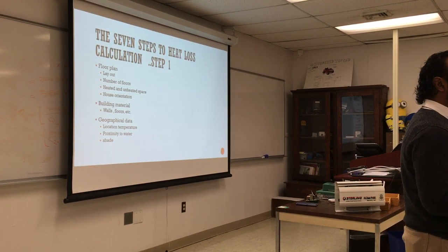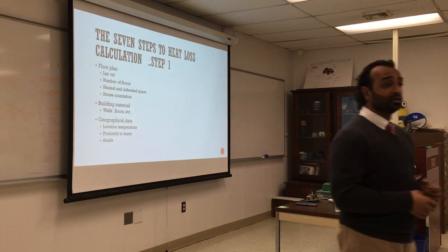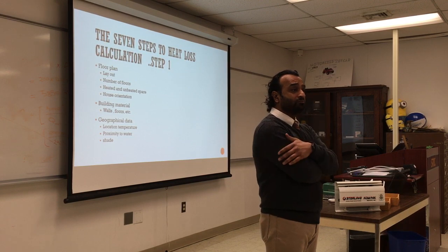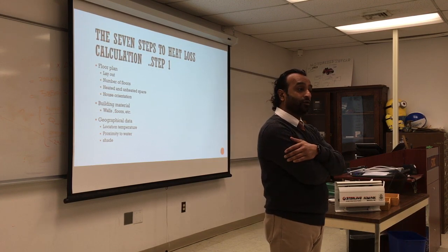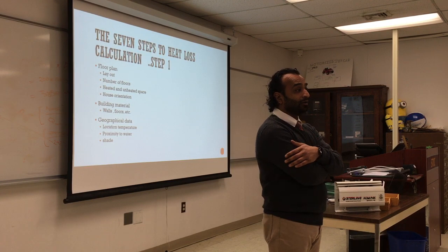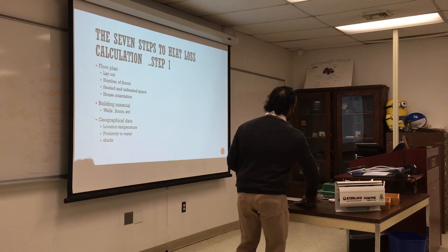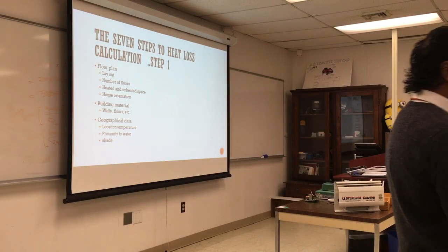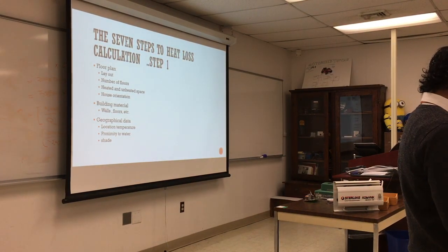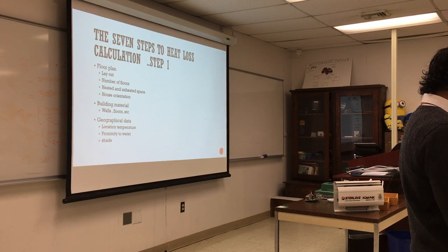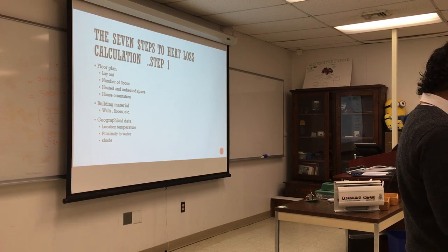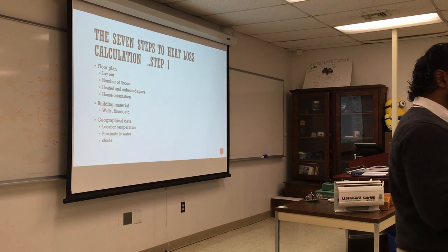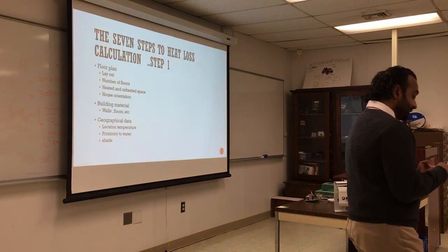That is a lot. If you think about it, if you're gonna have 100 BTU an hour, over 12 hours that you're heating the house, if you say it's 12 hours, not 24, that's gonna add up to a lot. Let's say it's 60,000 an hour. How much was your house? 60,000. Okay, 60,000, that's for 1 hour. So if we assume it's 12 hours, that's 720,000 BTUs.